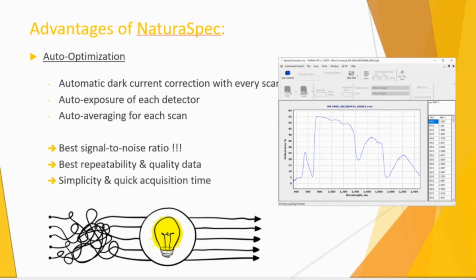When you take measurements with a spectrometer, there's a few things that need to be done. You have to compensate for dark current. So what you typically do is take a scan of a very dark sample, meaning no light. And whatever signal you get on that dark sample is really your noise, because theoretically, if you're in the perfect dark without any light signal, you would get no signal at all. But in reality, you do get some noise, even with a dark sample. So our program will compensate for that.